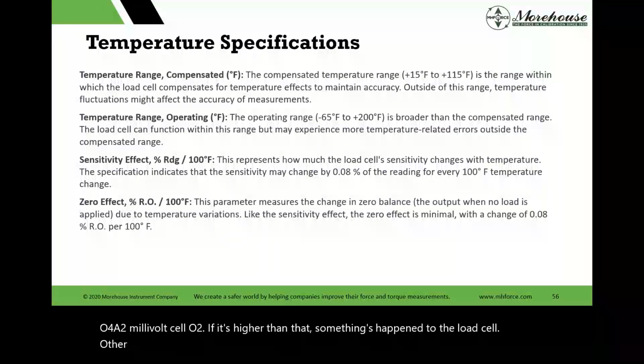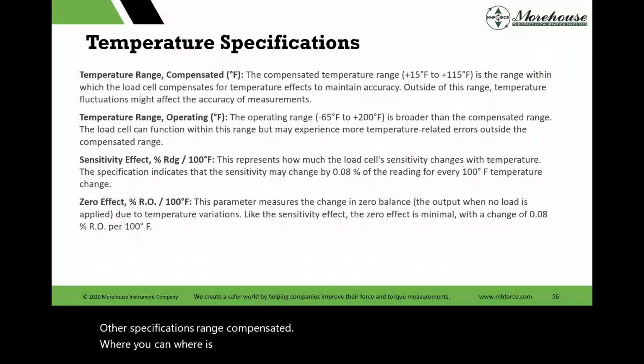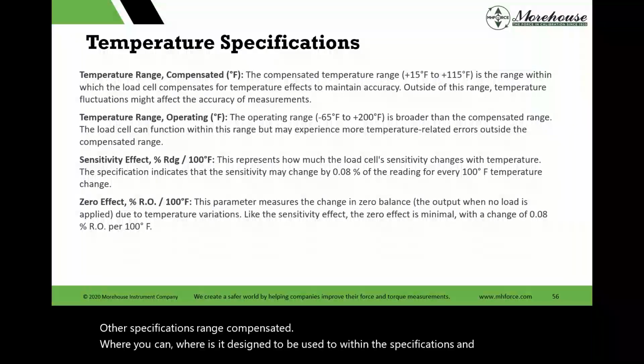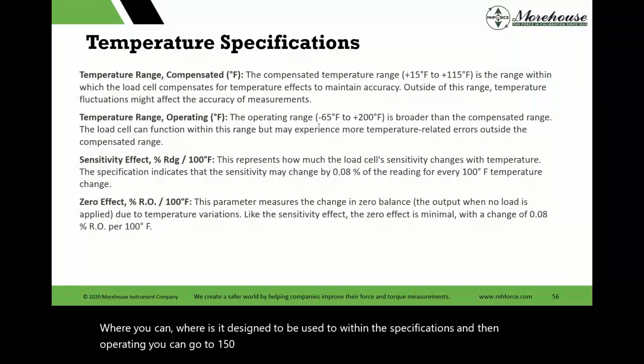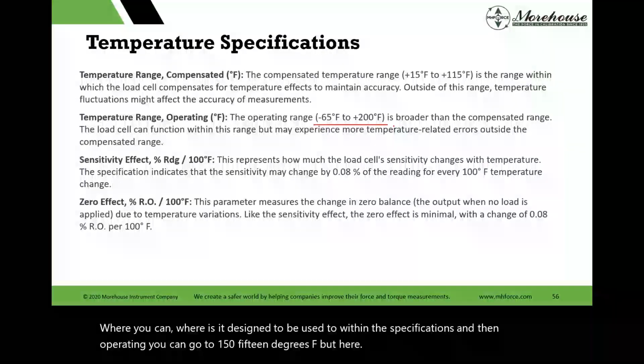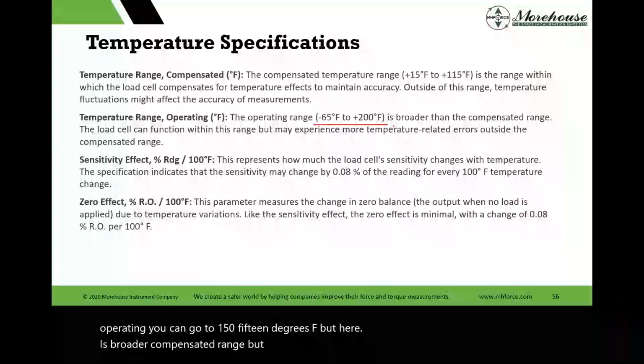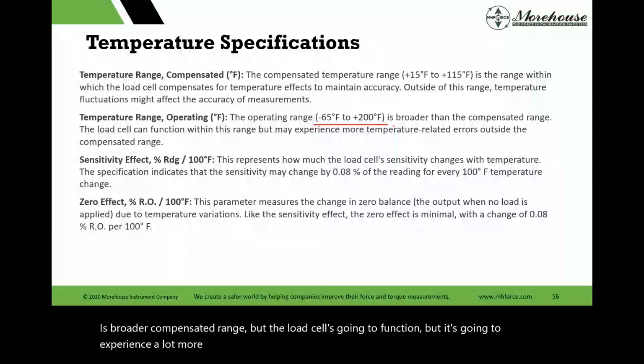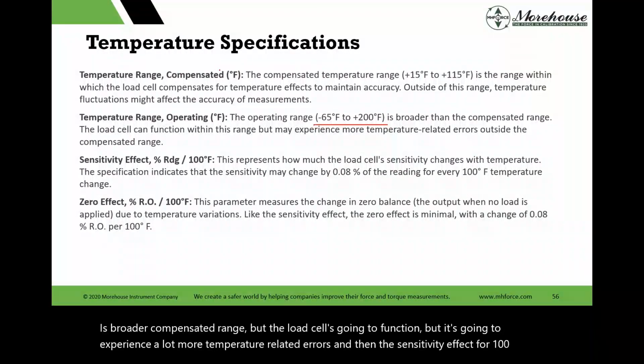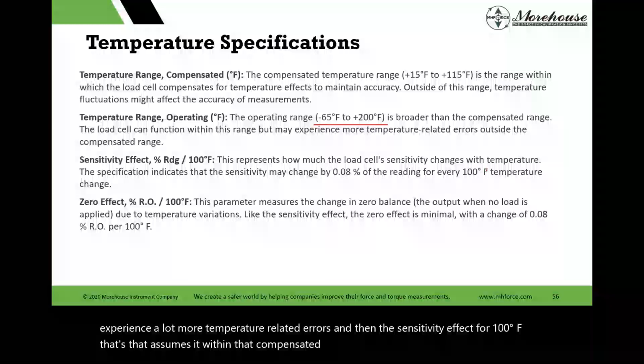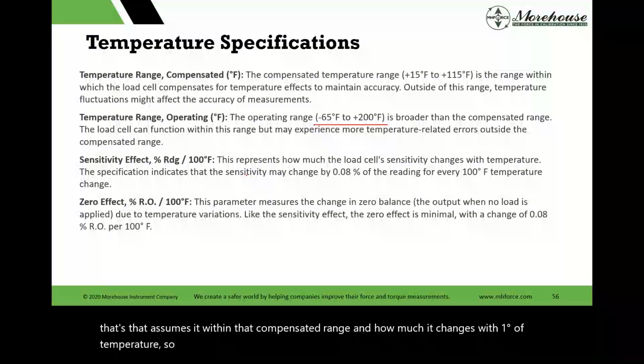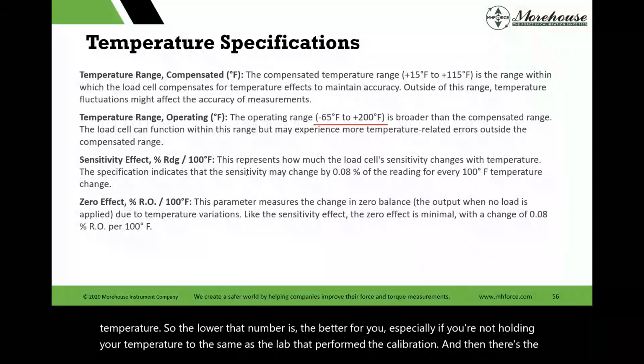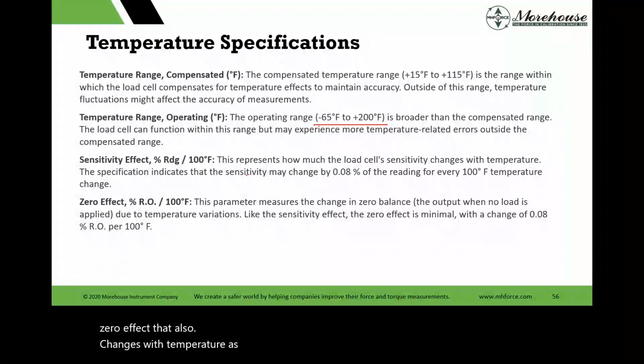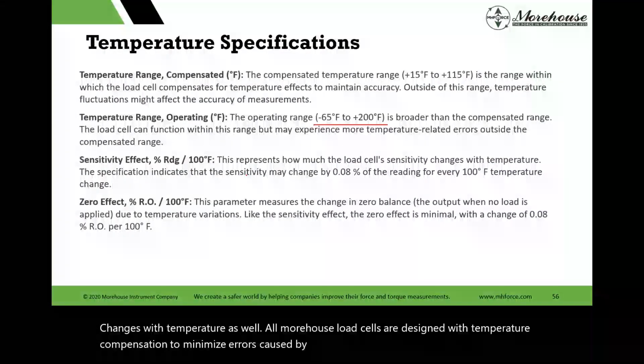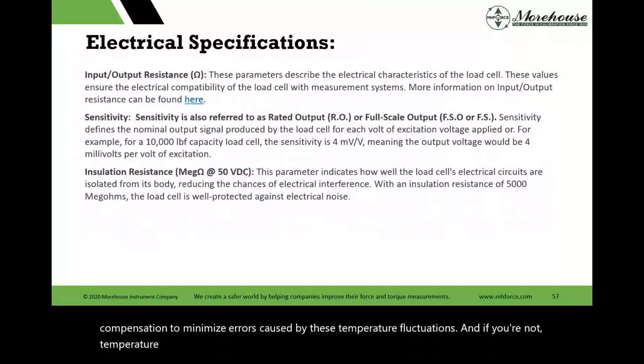Other specifications, range compensated, where it's designed to be used within the specifications. And then operating, well, you can go to 115 degrees F, but here is a broader range, where the load cell is going to function, but it's going to experience a lot more temperature related errors. And then the sensitivity effect per 100 degrees F, that assumes it's within that compensated range, and how much it changes with 1 degree of temperature. So the lower that number is, the better for you, especially if you're not holding your temperature to the same as the lab that performed the calibration. And then there's the zero effect, that also changes with temperature as well. All Morehouse load cells are designed with temperature compensation to minimize errors caused by these temperature fluctuations. And if you're not temperature compensated, you can have rather large errors.